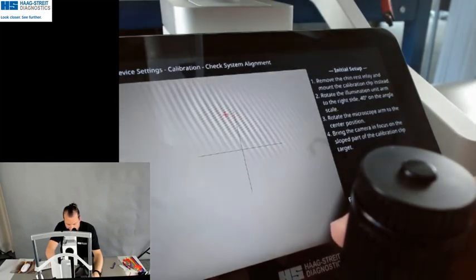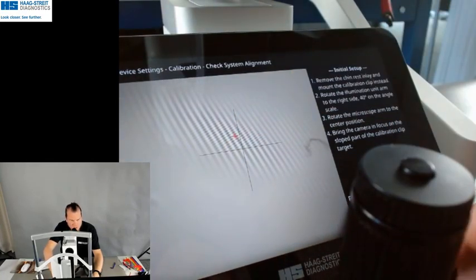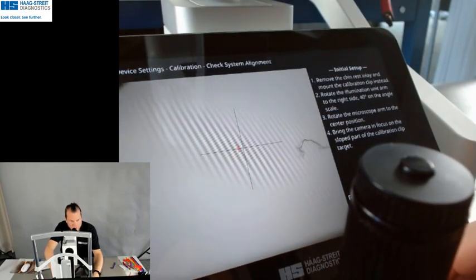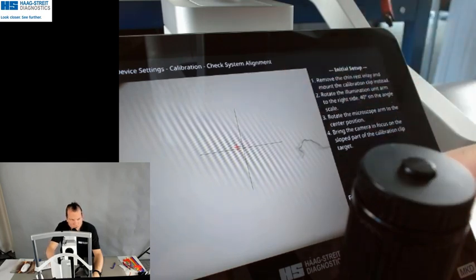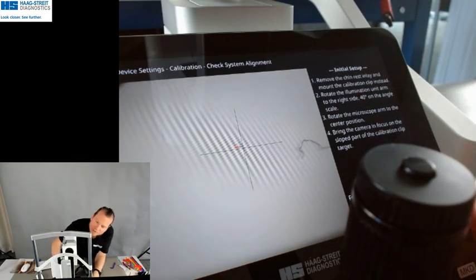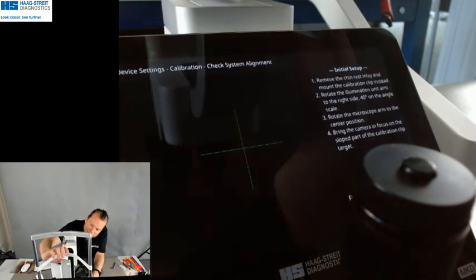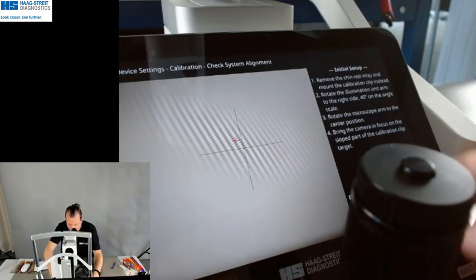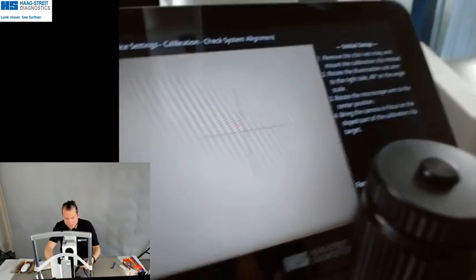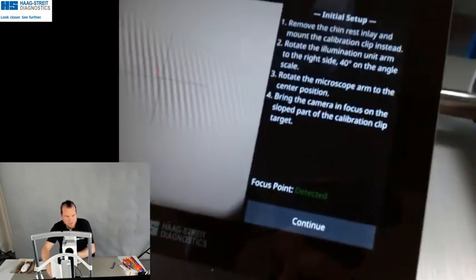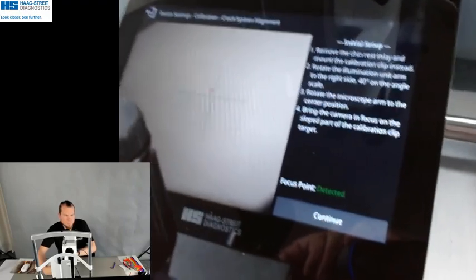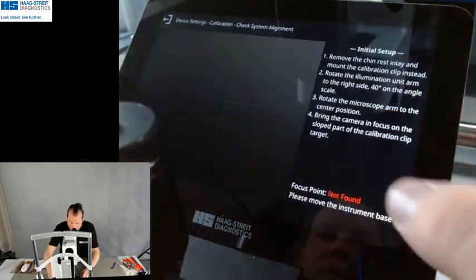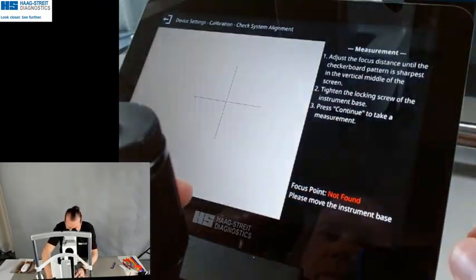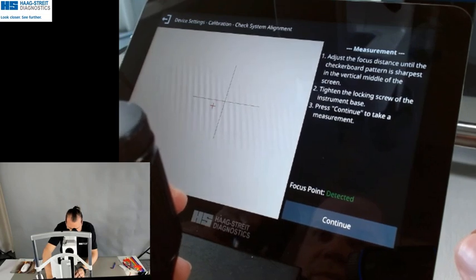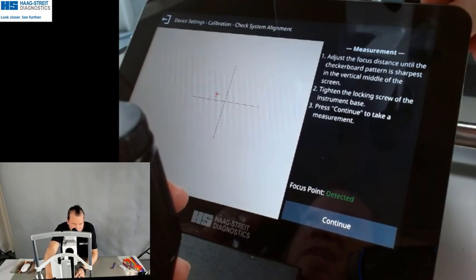First, finding the focus, you will see this little red cross. Just bring it onto the height of the crosshair from the screen. It also will tell you that it's detected. Once this looks good, so we have the detection on this side. Let's switch over here. We can continue. We make the fine alignment and we fix the instrument base.